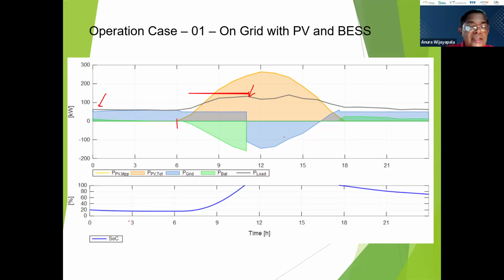And here I have inserted the state of charge of the battery. You can see early morning hours, battery has been set to not discharge beyond 20%, so it will stop discharging after reaching the 20% SOC. Here you can see it is almost delivering nothing now. So the grid power, blue color, is almost equal to load here.